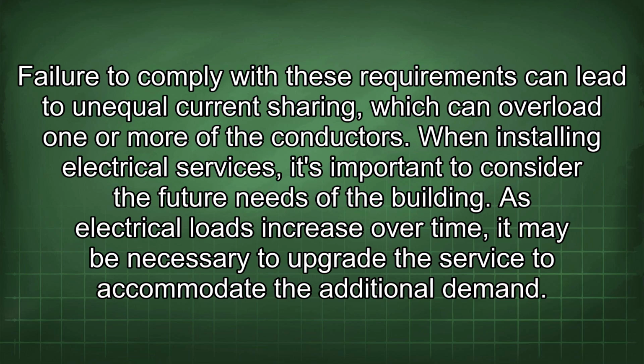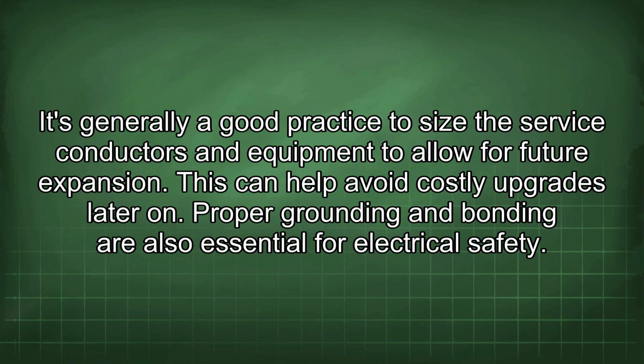When installing electrical services, it's important to consider the future needs of the building. As electrical loads increase over time, it may be necessary to upgrade the service to accommodate the additional demand. It's generally a good practice to size the service conductors and equipment to allow for future expansion. This can help avoid costly upgrades later on.